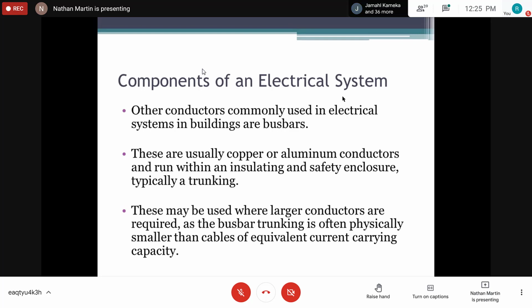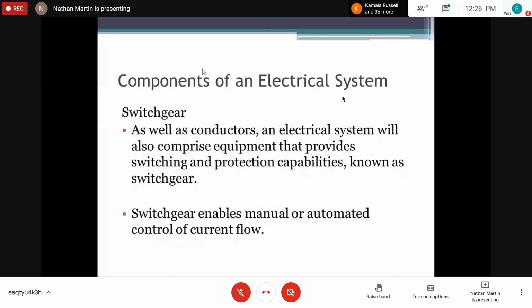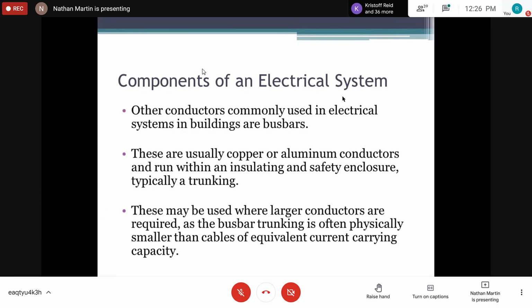They just have the bus bar trunking, and it looks much better. All right. So when we come to the switchgear, right? Sorry. The bus bar trunking you talked about, is that the aluminum metal one? Yes, but the bus bars are insulated from the metal by either ceramic material or thermosetting material, right? So you either use ceramic or thermosetting.